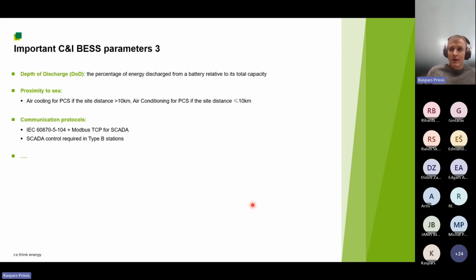Of course, there are also other important parameters in BESS. So it's depth of discharge. We already talked about this. For lithium iron phosphate batteries, this is up to 100%. Also important is how close this battery is going to be to the sea, because for the solutions that are closer than 10 kilometers, we must use air conditioning for PCS, not natural air or forced air ventilation, due to humidity reasons.